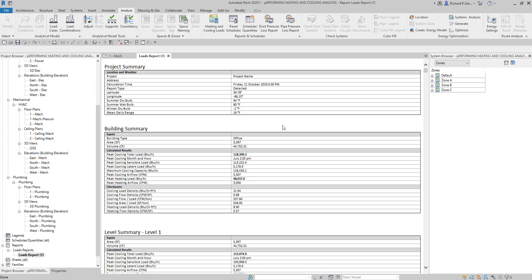Revit MEP performs a heating and cooling loads analysis using the integrated heating and cooling loads analysis engine. In this analysis, various factors are analyzed including the analytical and inner volumes of the spaces. As an engineer or designer, you can review the loads report to analyze the project, the weather, and the space and zone information of the building. Take note that you must perform a new heating and cooling loads analysis each time you modify the building, space and zone information, or make any changes to the model — otherwise this loads report will not reflect your changes.